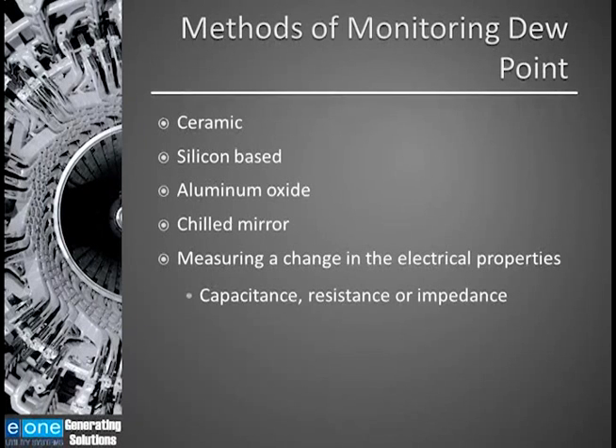Here are some methods, sensors or technologies that are used to monitor dew point. There's a ceramic chip type sensor, there's a silicon based sensor, and an aluminum oxide sensor. I don't believe that chilled mirrors have ever been used to monitor dew point in hydrogen cooled generators. The three sensors listed above are measuring a change in the electrical properties, whether that change be a change in capacitance, change in resistance, or a change in impedance.